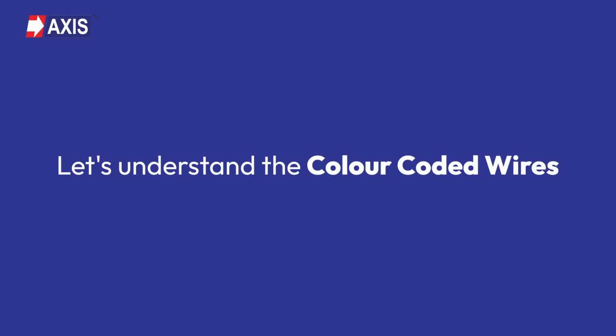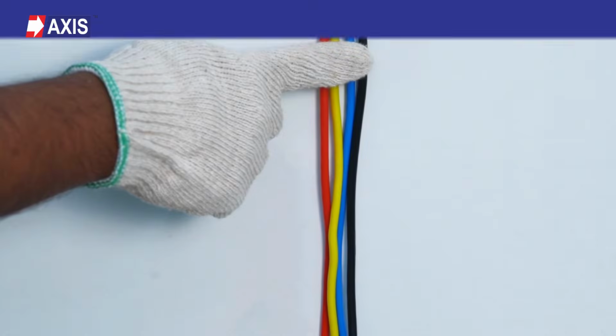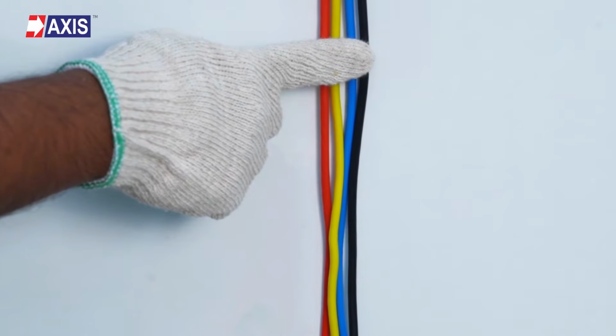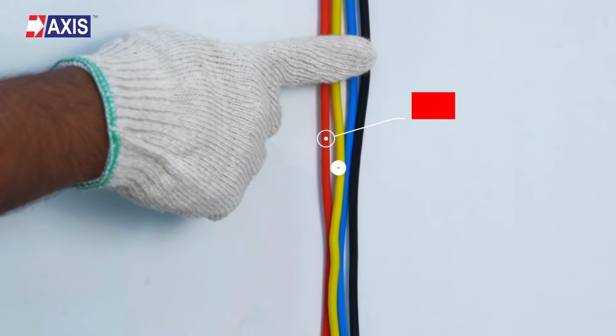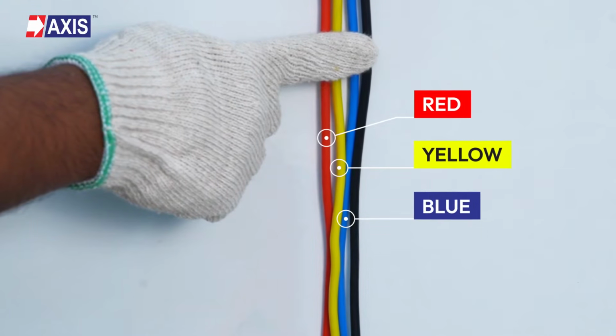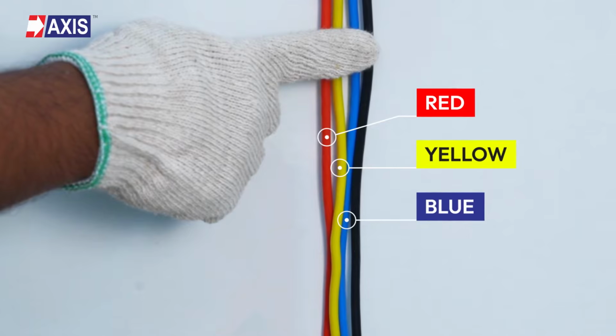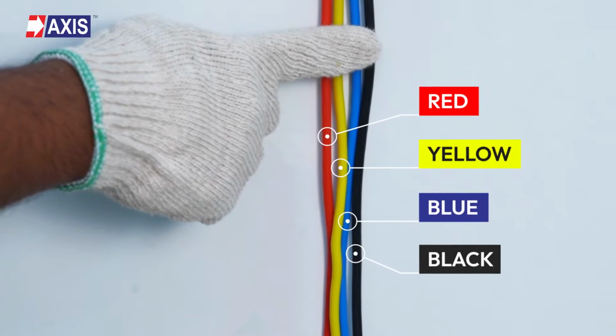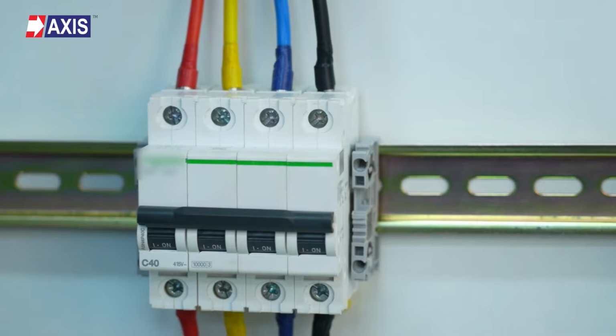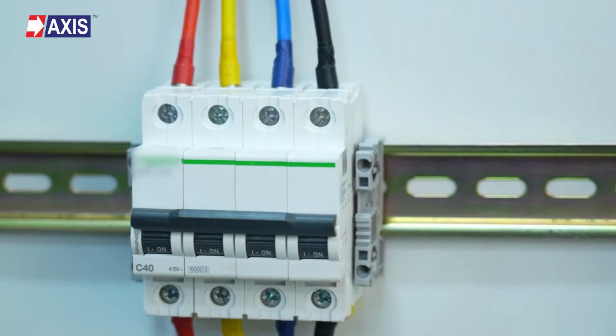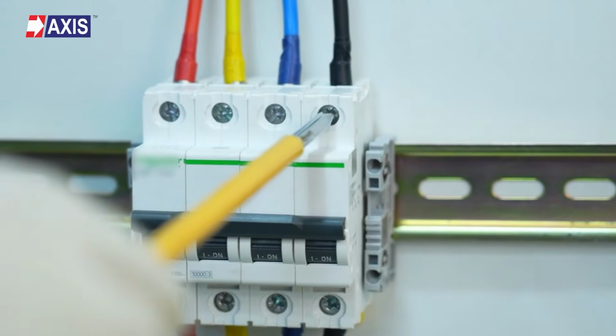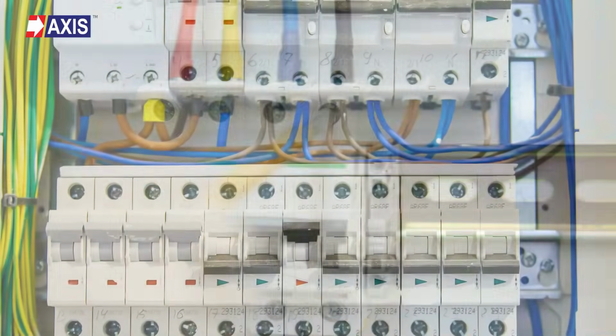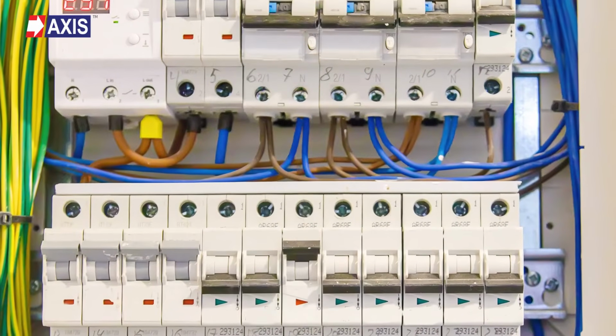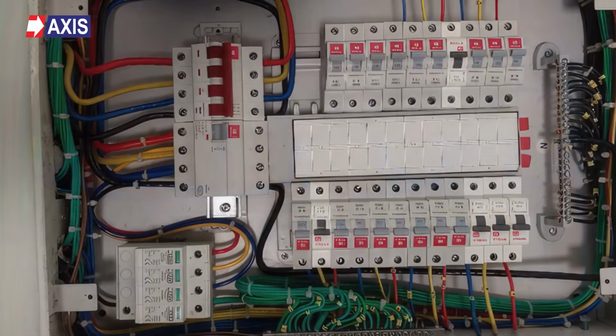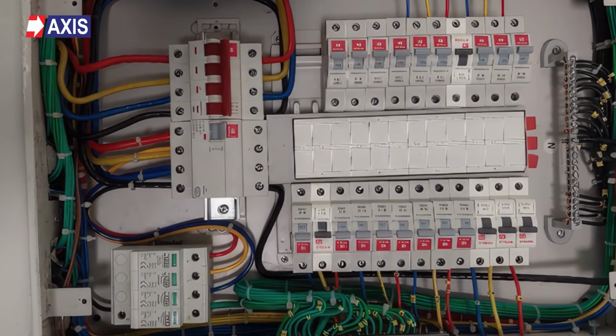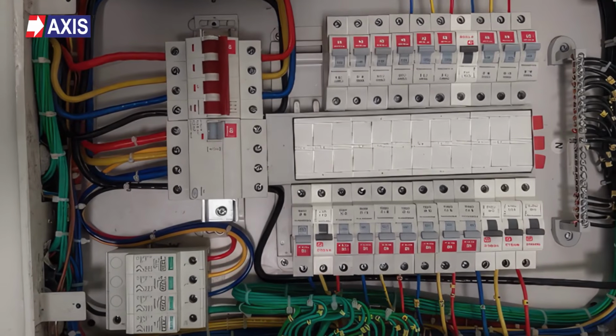Let's understand the color-coded wires. This is a 3-phase incoming system with neutral. The red, yellow, and blue wires are the 3-phase wires. The black wire is the neutral wire. Please note, we are installing this on a display board for ease of your understanding. The SPD can also be installed inside the main panel if there is enough space. Alternatively, it can be installed externally in a separate box connected to the main panel or distribution box.